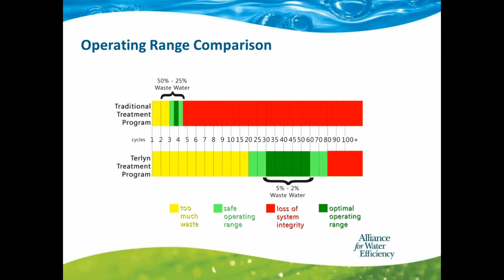So here's a way of looking at the operating range. What you see here, if you're operating a cooling tower without any water treatment program, then 100% of the wastewater is wasted. By implementing a traditional chemical treatment program, you are in fact implementing water conservation, because you will reduce the wastewater down to 50 to 25%. But at the same time, you're creating a very narrow window in which to operate and achieve complete system integrity, which is demonstrated by the area that's in green. That's what we call our sweet spot.